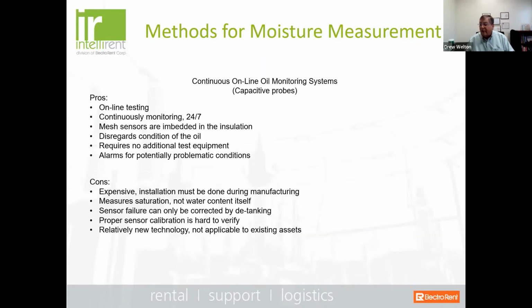Okay, there's some other methods as well, and this is becoming more popular. We'll see, especially with new transformers, where they're doing continuous online monitoring systems. And the technology here is actually starting to get much better. The good news is that you have continuous monitoring of moisture content, and this is actually a saturation point, and it disregards the condition of the oil. It doesn't require any additional test equipment, and you can, of course, set it for alarms if you happen to run into a situation where moisture is starting to get too high.